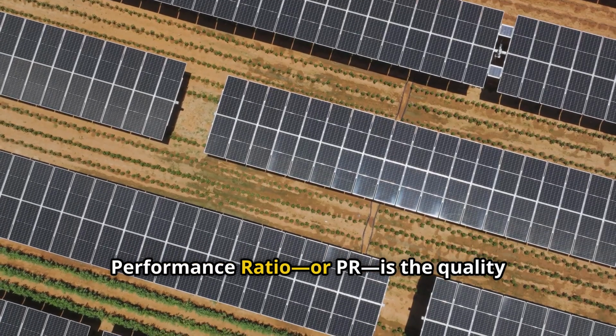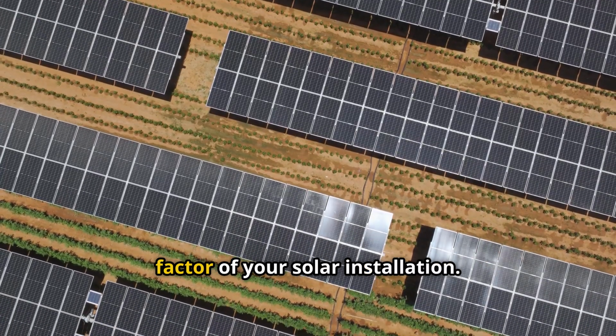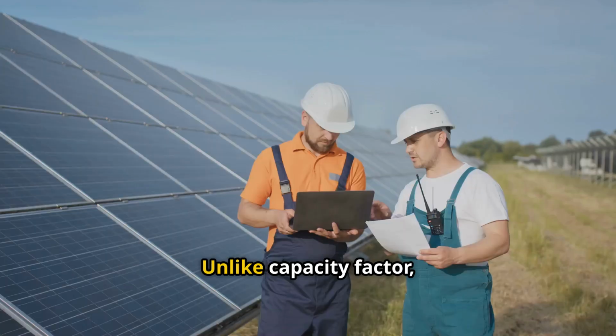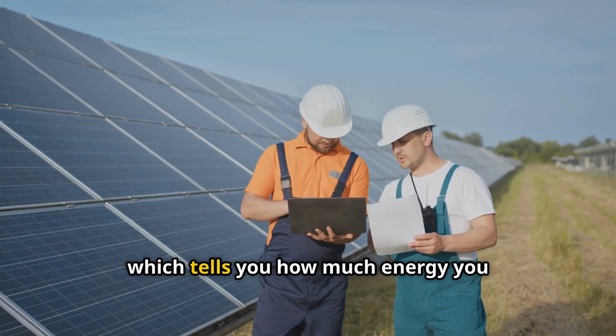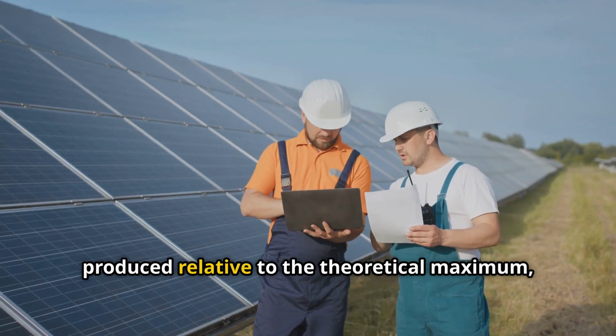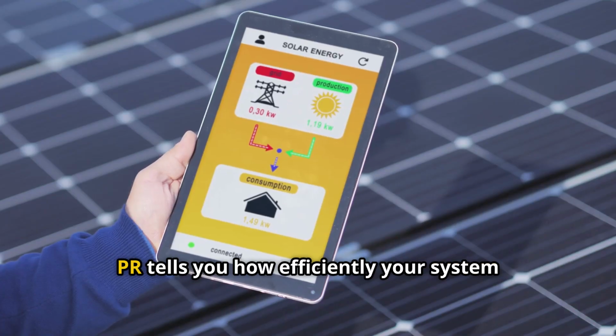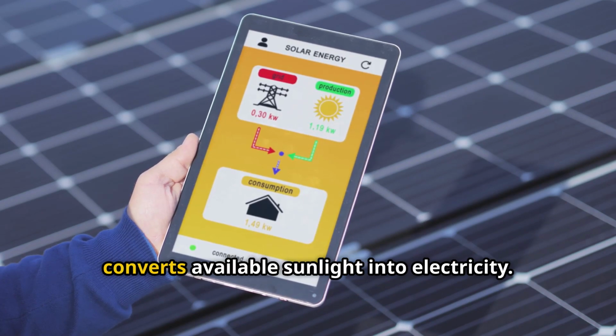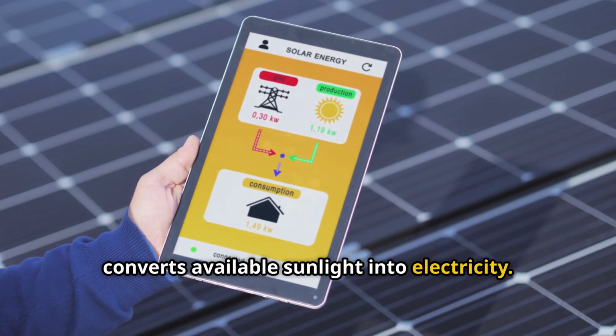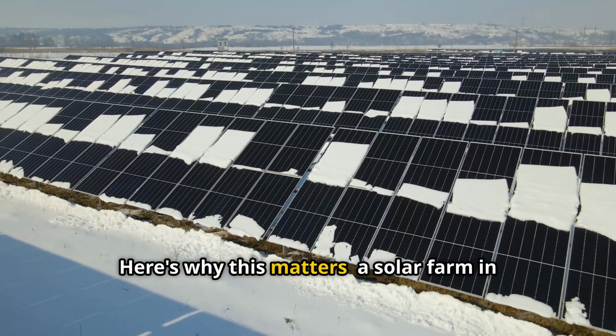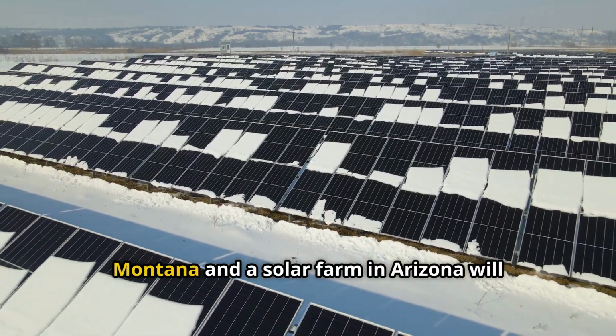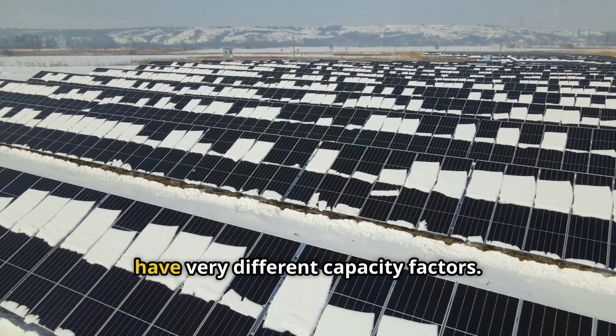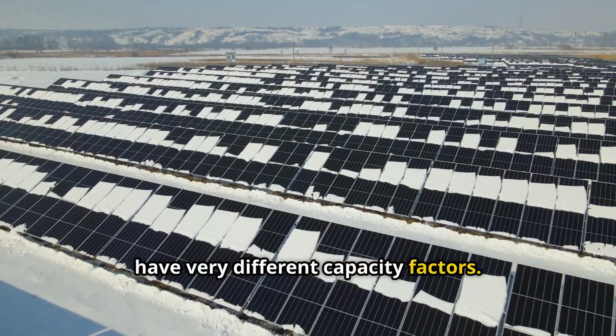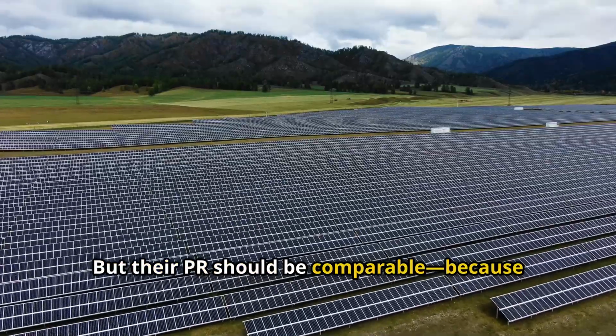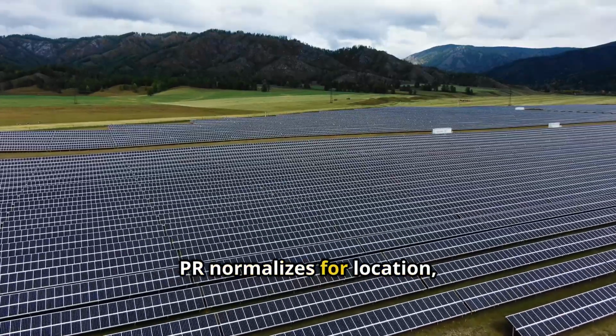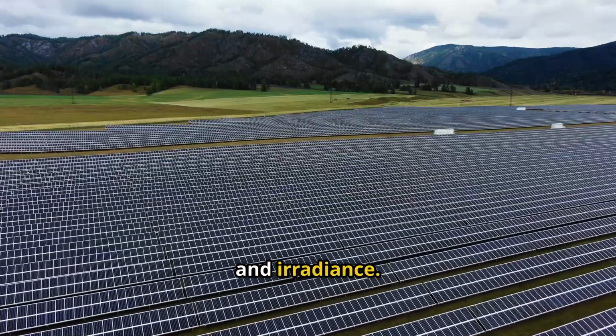Performance ratio, or PR, is the quality factor of your solar installation. Unlike capacity factor, which tells you how much energy you produced relative to the theoretical maximum, PR tells you how efficiently your system converts available sunlight into electricity. Here's why this matters. A solar farm in Montana and a solar farm in Arizona will have very different capacity factors, but their PR should be comparable, because PR normalizes for location, weather, and irradiance.